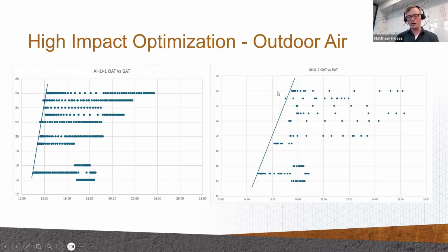No matter what it's doing, no matter how hard it's running or how long it's called on for, we can set aside everything about control cycling, everything about response times. It just never gets there. If it's 24 degrees outside, it's pushing supply air over 16. It's not doing what it ought to do. And we could find that with 3 data points.